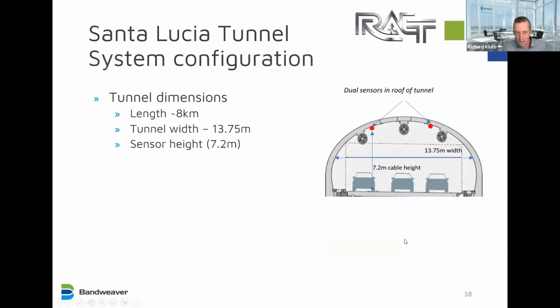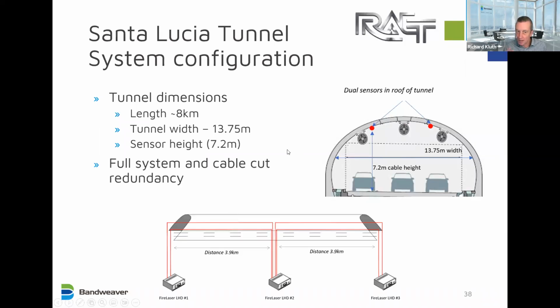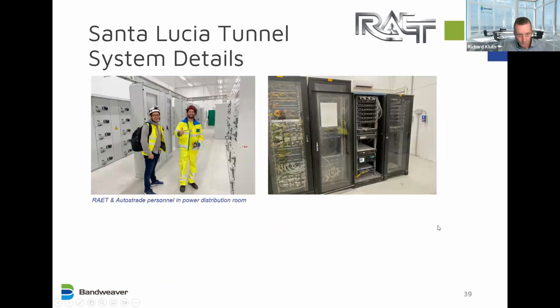So the system configuration: the tunnel's 8 kilometers long, 13.7 meters wide. The sensors were positioned at 7.2 meters at 2 locations across the tunnel. And we had full system and cable cut redundancy. So when any system is taken out of service or there is any damage to any of the cables, you still have full functionality. You would receive an alarm, but they continue to operate.